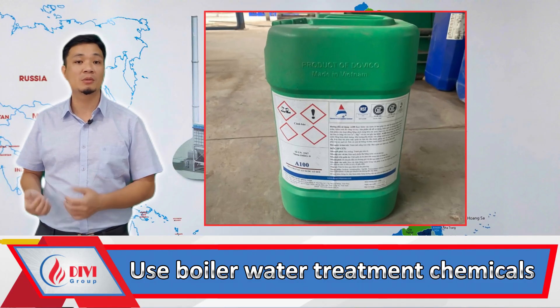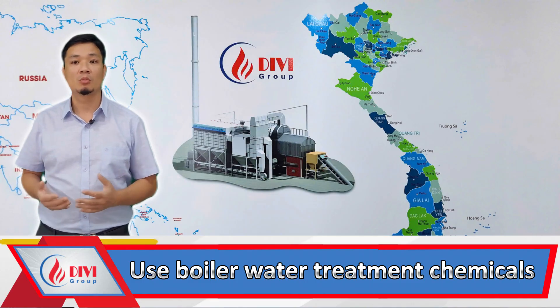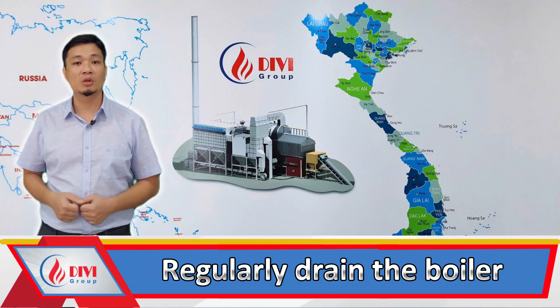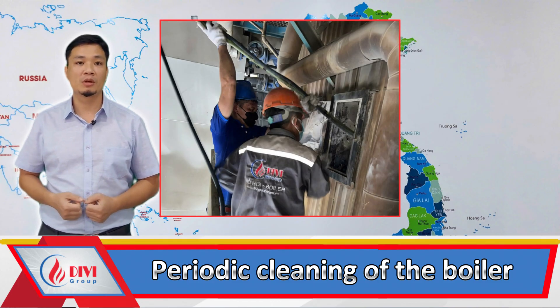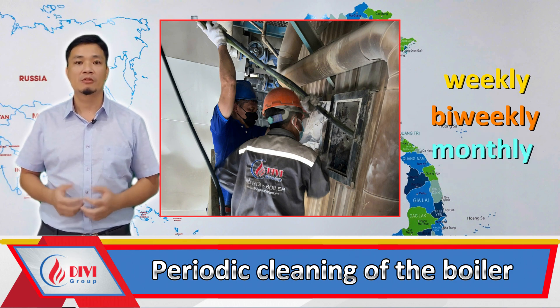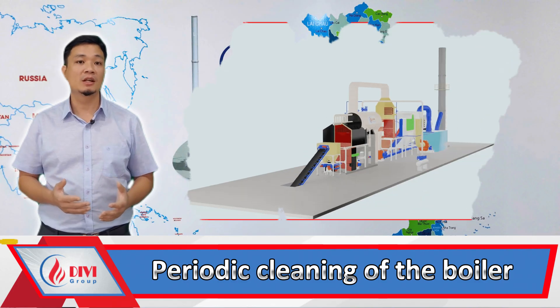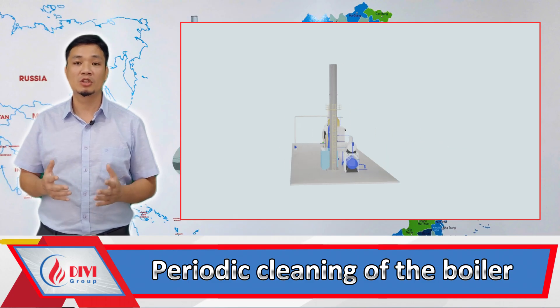First, use boiler water treatment chemicals — you can find more details in the video 'Why you must use water treatment chemicals for your boiler' on DIVI's channel. Second, regularly drain the boiler — check out the video 'Why you must drain your boiler' on DIVI's channel. Third, periodic cleaning of the boiler: ensure that the heat exchange equipment and flue gas ducts are cleaned regularly — weekly, bi-weekly, or monthly. If the factory cannot stop the boiler for periodic cleaning, DIVI offers a solution for continuous cleaning while the boiler is still operating. This technology allows for cleaning the heat exchange equipment in just five to ten minutes without shutting down the boiler, which does not affect production.